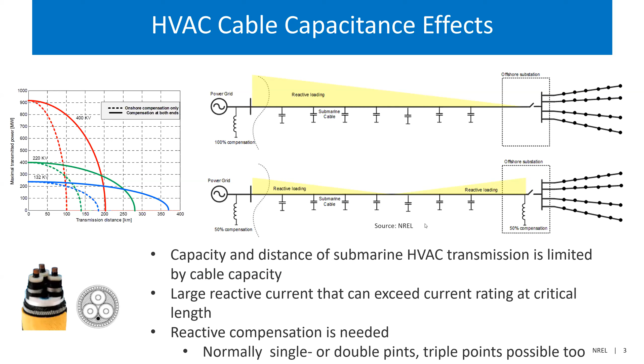To increase the distance, people use shunt compensation that can be at one end of a transmission or at both ends of a transmission. In some cases, it can even be at triple points. You can have a shunt compensation in the middle of a transmission cable. So the use of shunt compensation is essentially a measure to postpone the use of HVDC. But again, you can utilize this only until a certain distance, after which HVDC becomes a more economic solution.